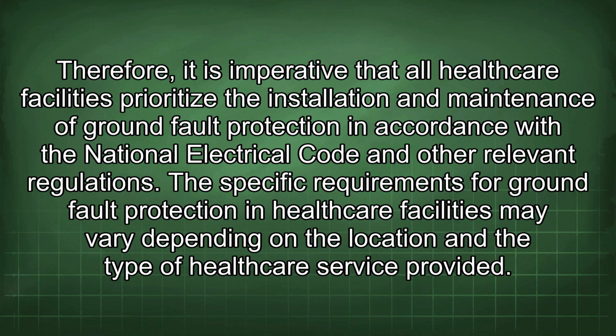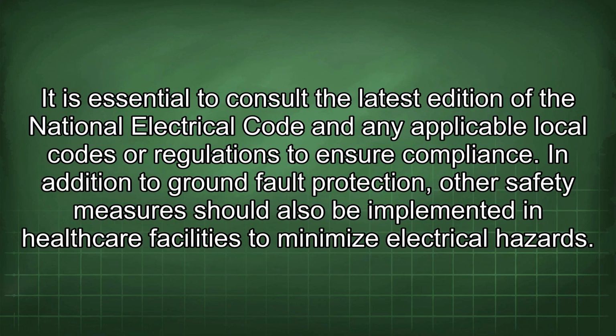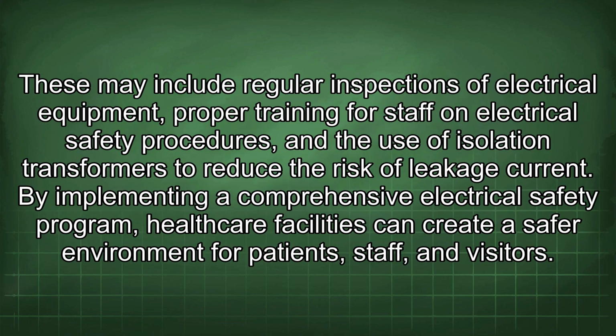The specific requirements for ground fault protection in healthcare facilities may vary depending on the location and the type of healthcare service provided. It is essential to consult the latest edition of the National Electrical Code and any applicable local codes or regulations to ensure compliance. In addition to ground fault protection, other safety measures should also be implemented in healthcare facilities to minimize electrical hazards. These may include regular inspections of electrical equipment, proper training for staff on electrical safety procedures, and the use of isolation transformers to reduce the risk of leakage current. By implementing a comprehensive electrical safety program, healthcare facilities can create a safer environment for patients, staff, and visitors.